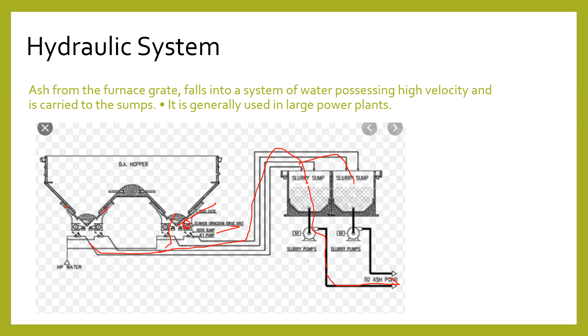Now under this slurry sump again you have slurry pumps which pump this bottom ash mixed with the water, basically the slurry, to the ash ponds. So this is how this thing works. There are pneumatic gates here which get opened. Generally these are manually operated, not automatic. So the mechanic or the boiler handler comes here, he operates the button, the gates open and the ash comes down. So this is how it works.